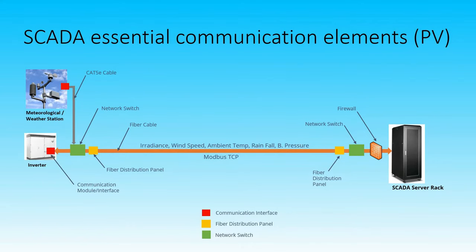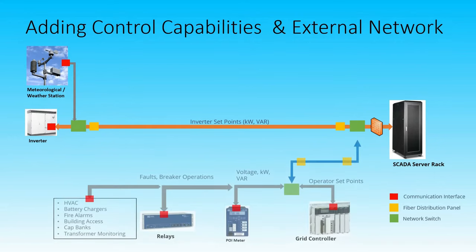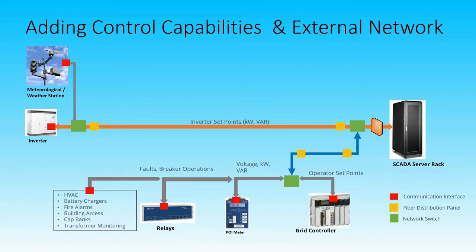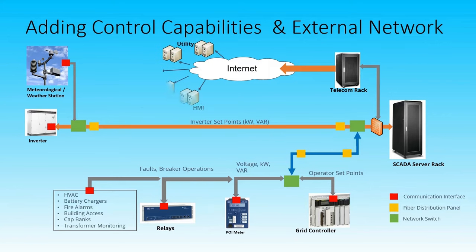In addition, live data parameters such as irradiance, wind speed, and ambient temperature — all relating to your weather station on the left — are also being collected. Adding more functionality such as controls, we now have grid controllers and relays that enable the user to send setpoints and breaker operations. With those information available on the SCADA server rack, you can also configure it to send those parameters out to the internet. Once configured properly, your data is accessible anywhere and remote operators can access the site remotely, transmitting the data over the internet.